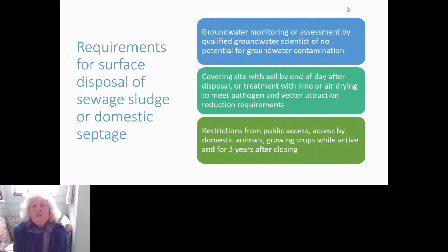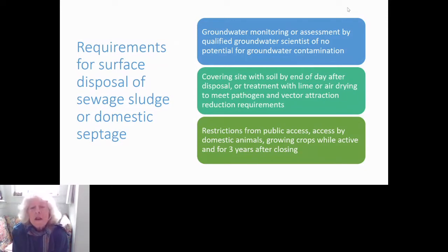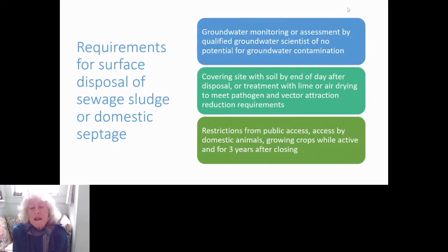There are also requirements for restricting public access and access by domestic animals. You need to restrict access for three years after the final septage has been disposed. This was an issue at the Hoopa lands site because they had a fence, but it wasn't really enough to ensure there wasn't any public access. There's also a prohibition on growing crops on the site while it's active and for three years after it's closed.